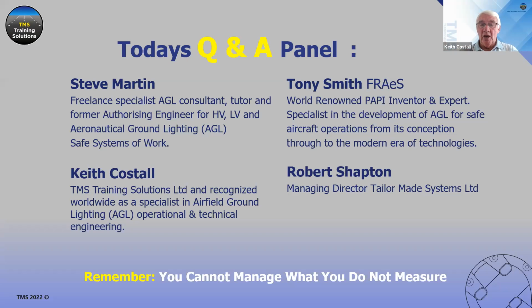So that actual value of current that will blow someone off is very debatable. In excess of 10 milliamps is the danger, because that's when we cannot let go. So that's all I'm going to say, because there is no fixed value of current at which you get blown off. You either stay holding it and the current flows through you, and potentially your heart gives way, as we've shown on the pictures in one of the presentation slides, or you get blown off. But if you get blown off, the chances are you've got burning. So it's a mixture of voltage and current, which is the key issue.